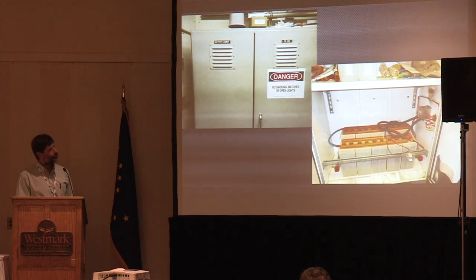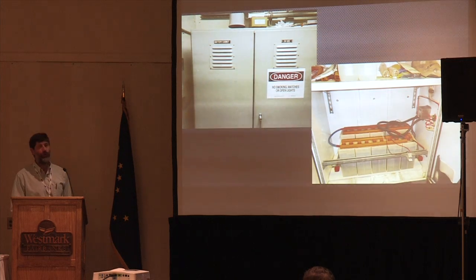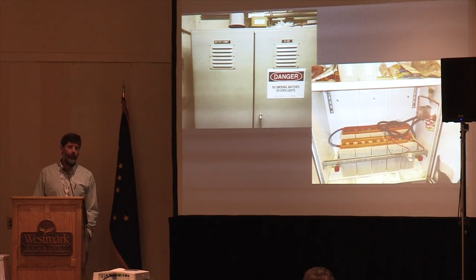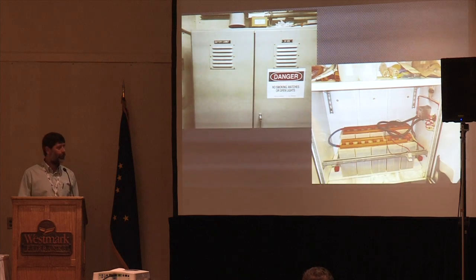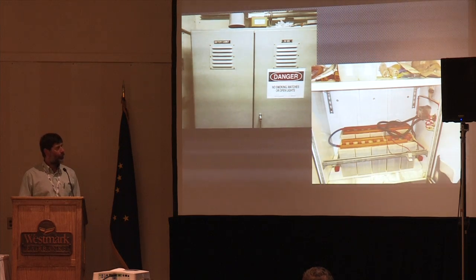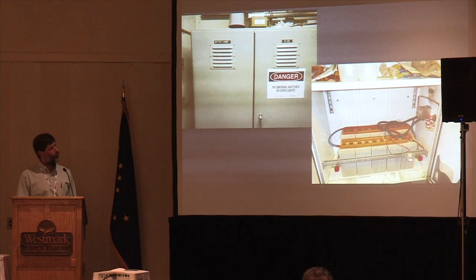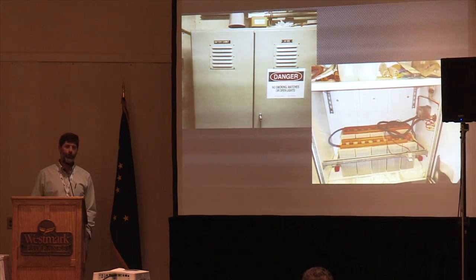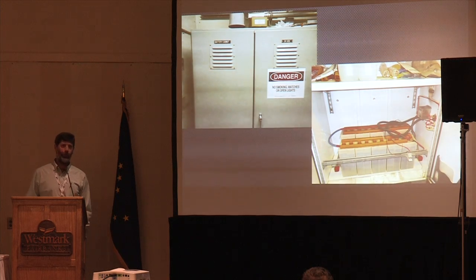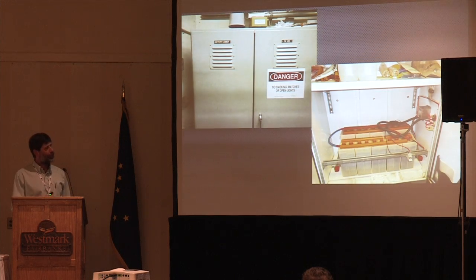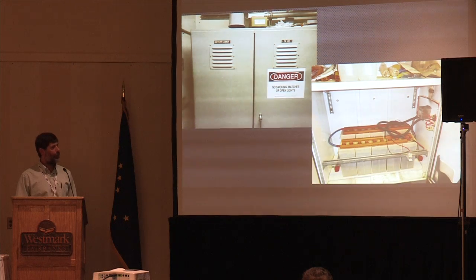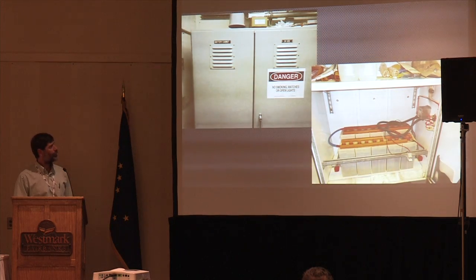We put in a bypass feeder. There's a battery charging system, just like you'd have in your garage if you wanted to charge your car batteries. That keeps those batteries topped up, running off AC power. But we also have an outlet and a switch so that when you draw the batteries down to a point where you can't start your engines anymore, and it's cold and dark and nothing's running, you can always hook up a 5 kW portable generator and recharge the batteries.